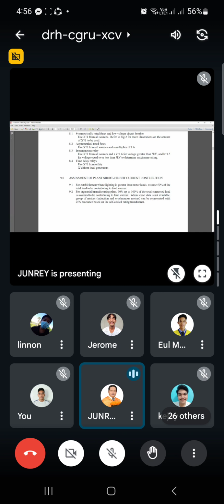Okay? Then for industrial or manufacturing plant, 90% or up to 100% of the total connected load is assumed to be contributing to the fault current. So for industrial and manufacturing. And then, where exact data is not available, for example, wala ka kahibaw sa iyang data, and you have the induction and synchronous motor, pwede na it can be represented by a 25% reactance value, or j0.25.